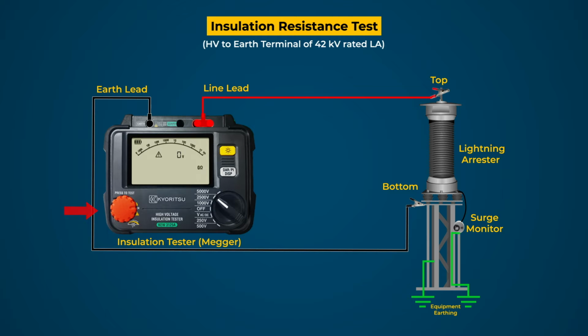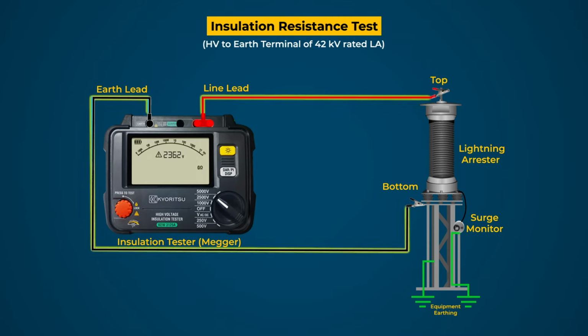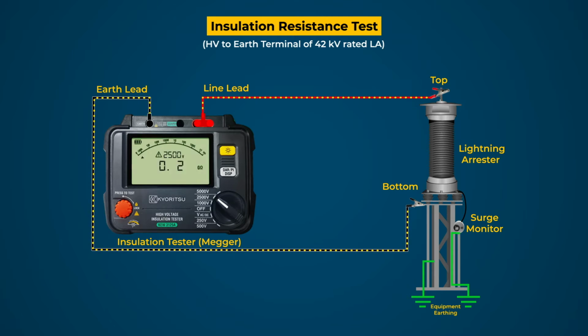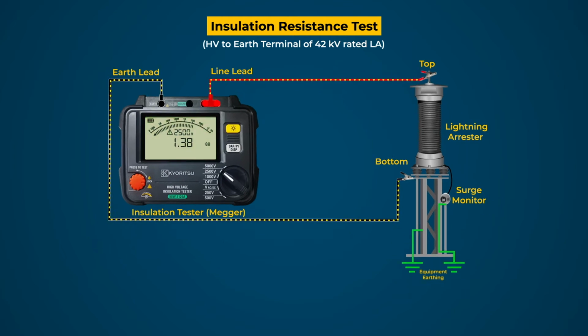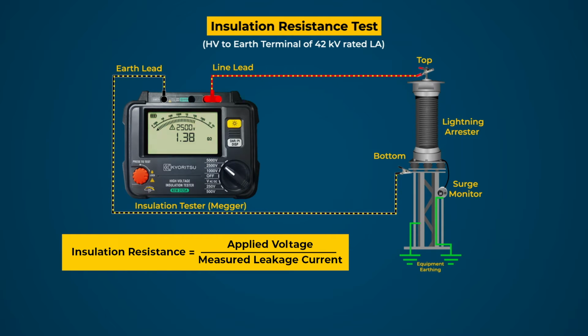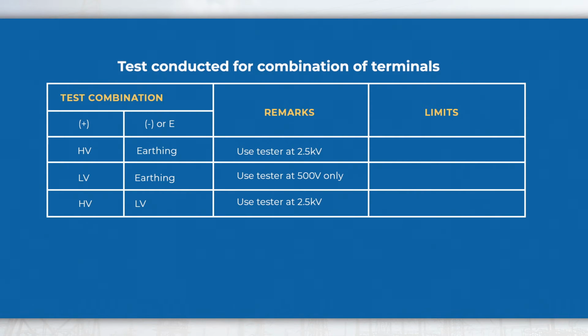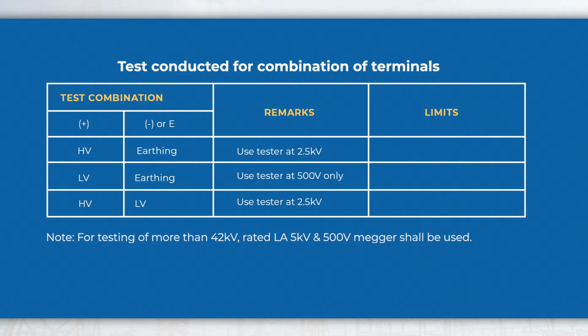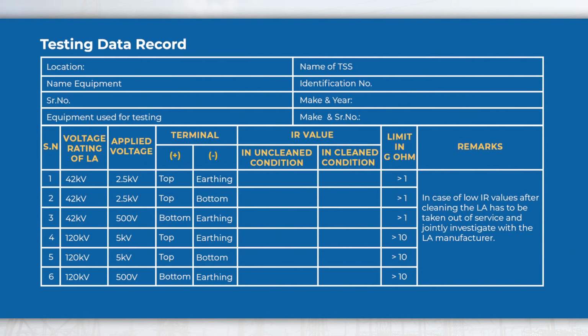Now on pressing the test button of the tester, 2.5 kV DC voltage is applied across the HV and earthing. As a result, leakage current will flow in the circuit, and the tester will measure this leakage current and calculate the insulation resistance value by the ratio of applied voltage and measured leakage current. Record the displayed value of IR and compare the value with earlier records or OEM recommendations. If found less, investigate the issue and rectify it. The same test to be conducted for the following combination. Testing data may be recorded in this format for further investigation and future reference.